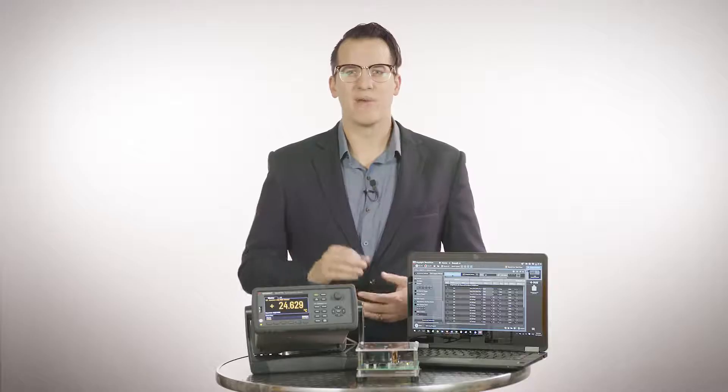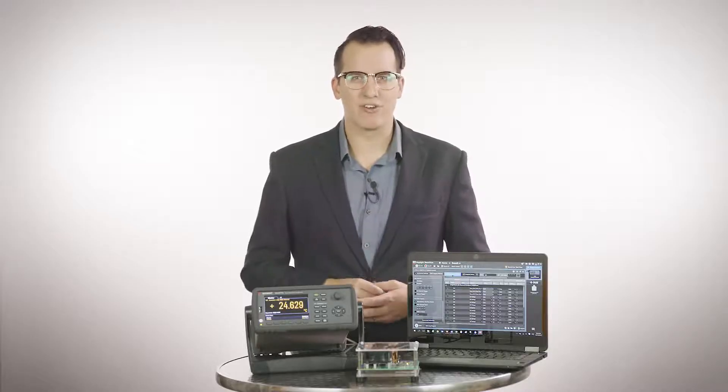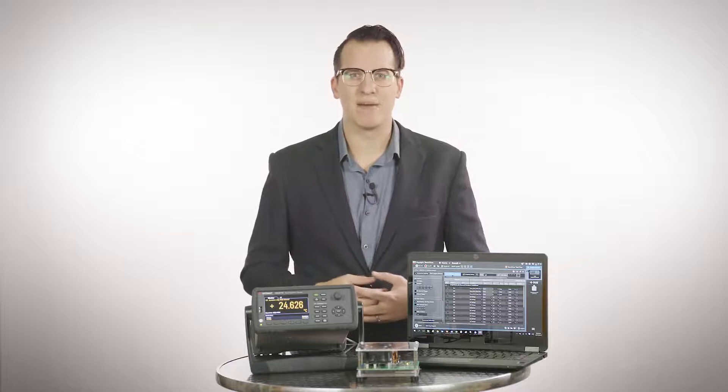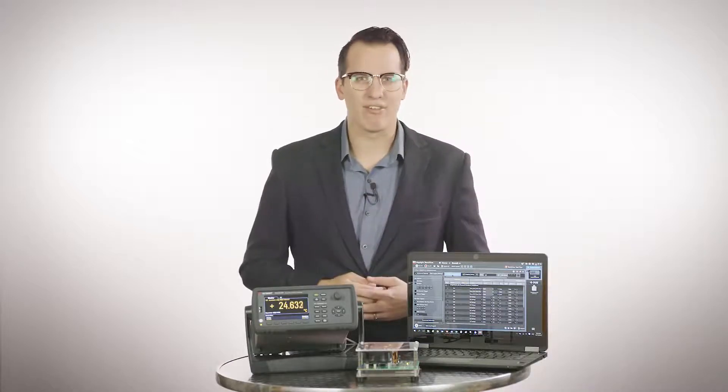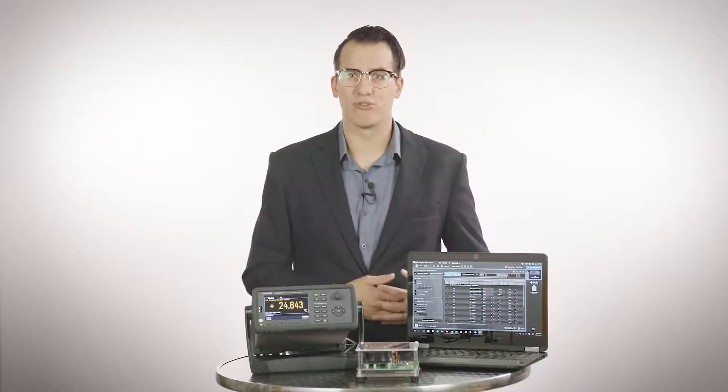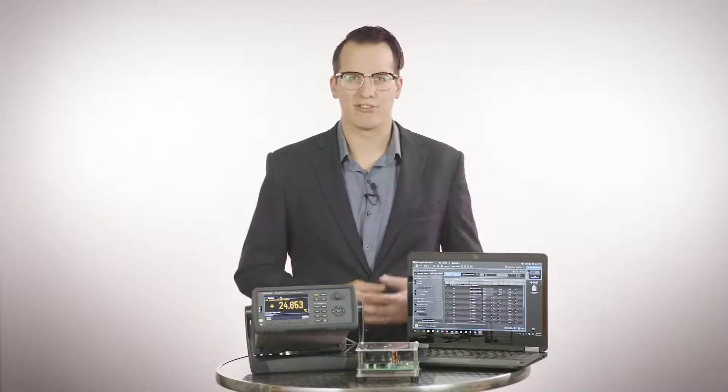The DAQ 970A also has up to 90% better accuracy for voltage, current, and resistance measurements. It comes with a new auto calibration feature which compensates the internal DMM and the new DAQ M907A multi-function module for drifts caused by time and temperature changes.